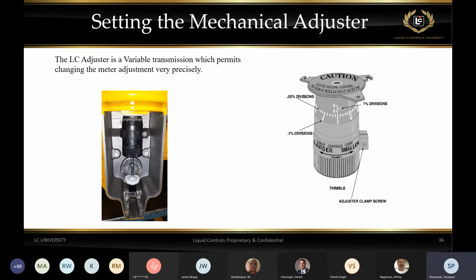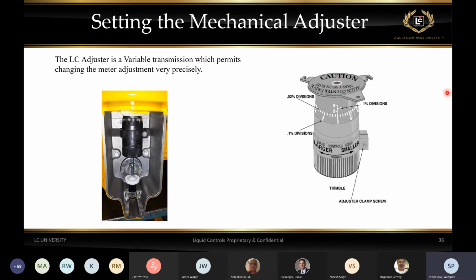The device in a meter that allows us to do that is an adjuster. This is an adjuster right here. A lot of people call it a calibrator, a lot of people call it a micro adjuster. It is really a variable transmission that allows us to adjust the meter reading very precisely. If you look at this adjuster, there's a hex shaft going up that drives the adjuster, and on the top of it is its output, which is what drives the counter. In very basic terms, it's a transmission that allows us to change the output speed that goes into the counter, and we can change this output speed very, very precisely to adjust the calibration, the accuracy of the meter.